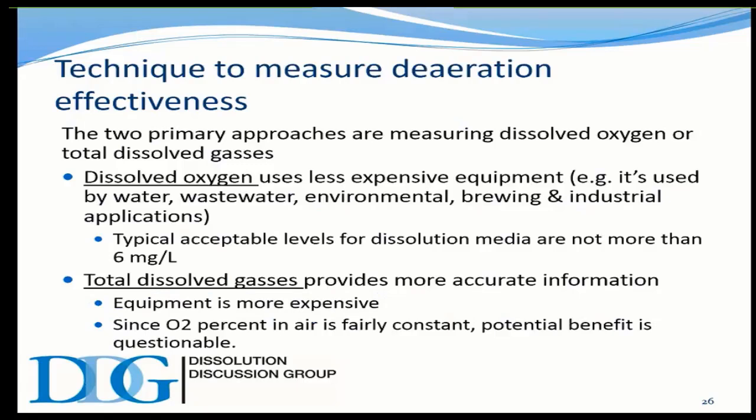In the meantime, we've received another question. Everybody's got a question now, which is great. I love it. The question reads, for our PVTs, we perform in-house paddles only. My primary indicator the media is deaerated properly is by ensuring there are no bubbles on or under the paddles and ensuring they don't redevelop. I haven't had to do the PVT for the basket apparatus, but we are planning on doing so in the future. Do you have any visual tips or tricks to ensure the media is deaerated for the baskets?